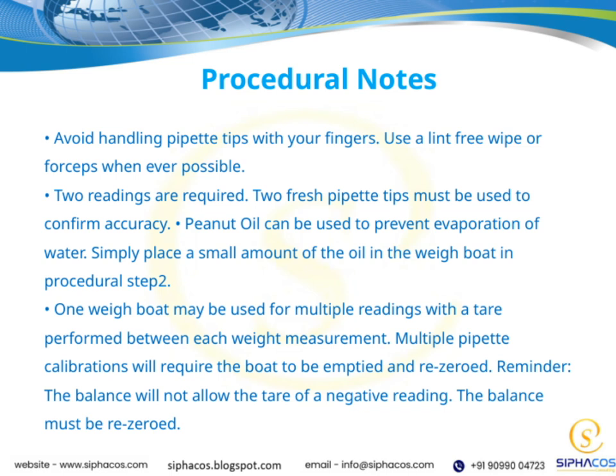Regarding evaporation, peanut oil can be quite helpful. Just place a small amount of it in the weigh boat before weighing water. This creates a barrier that prevents water from evaporating during the process. You can use one weigh boat for multiple readings by performing a tare between each measurement. However, if you're doing multiple calibrations, you'll need to empty and re-zero the boat each time. Remember, the balance won't allow you to tare a negative reading, so always re-zero the balance before starting a new measurement. Overall, these steps help maintain precision and consistency in our measurements, which is vital for the integrity of our results.